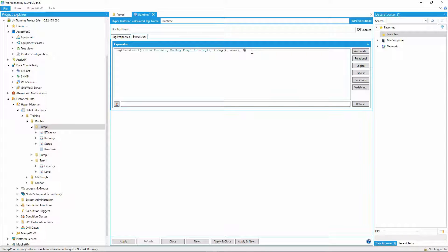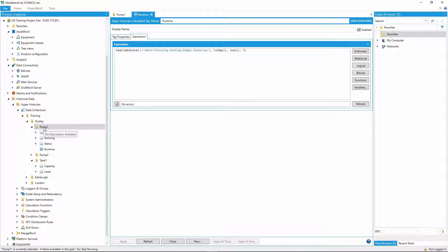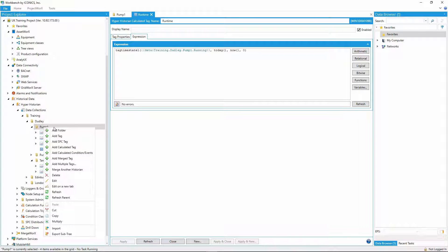I'll set the quality to zero, so that any data points available will return a value for me. And that's it, the calculation will start evaluating and being stored directly into the Historian every minute.